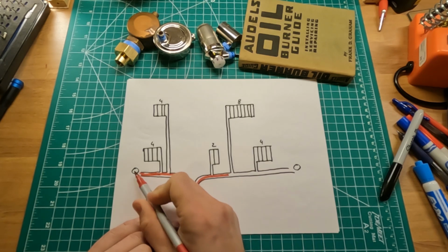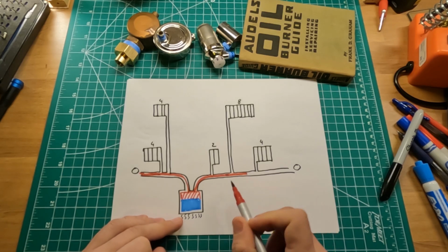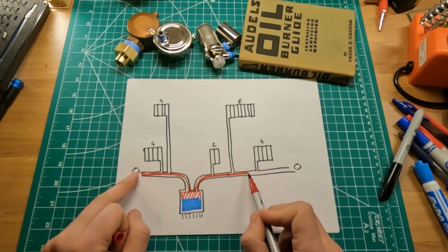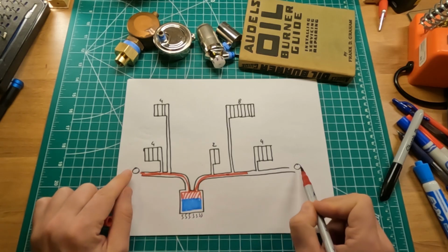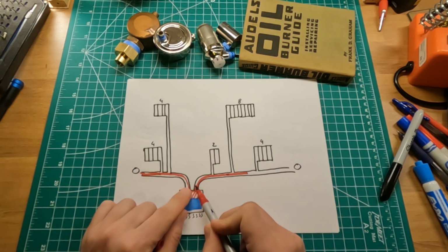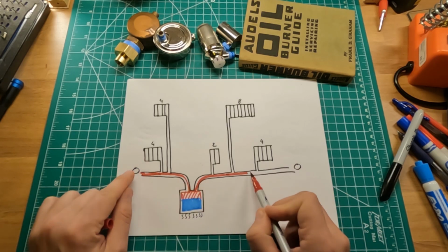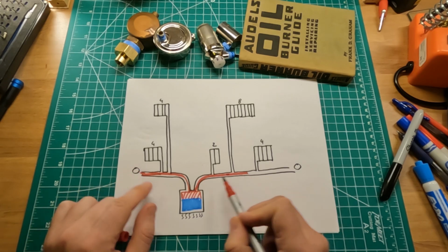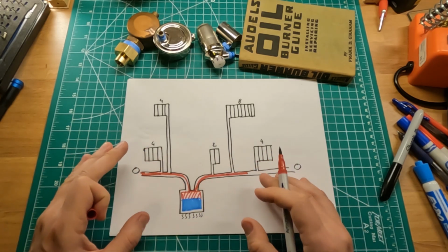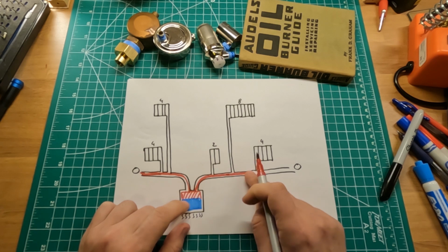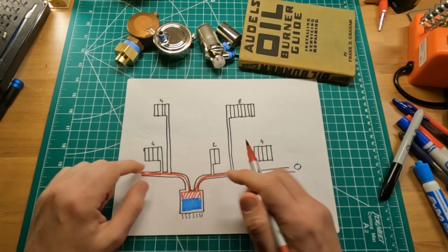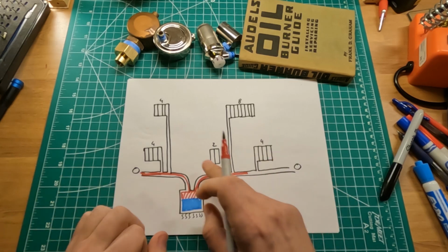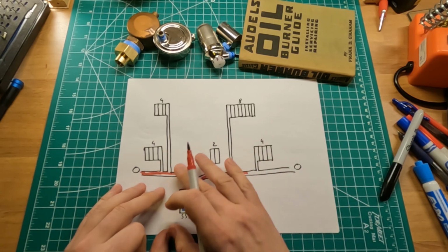Let's go all the way to this vent. Maybe this one will go all the way here. So as you can see, this is an equal distance because the venting rate on those two mains is the same. Because of that, it's equal distance from the boiler. So in other words, if all things are equal, you're going to have the same amount of steam in this main and then this main. And of course, when you have that steam, more steam gets produced, and all the other radiators start filling up.